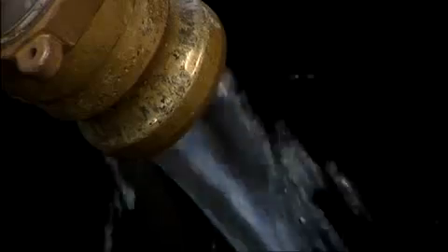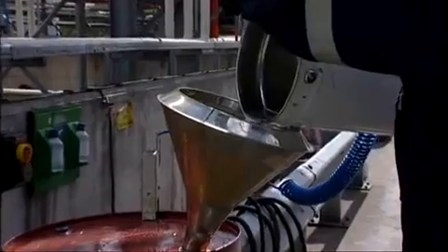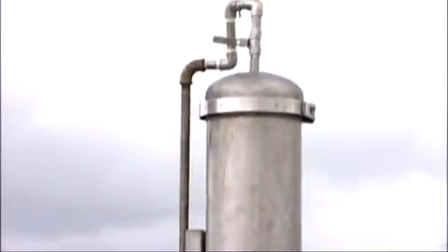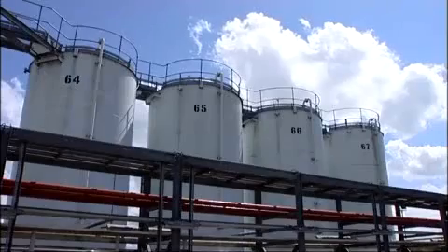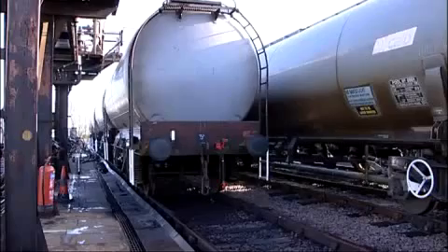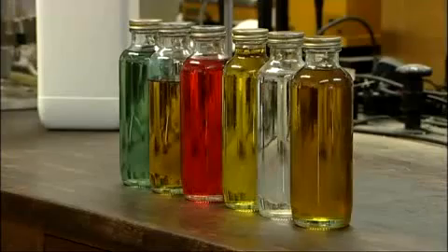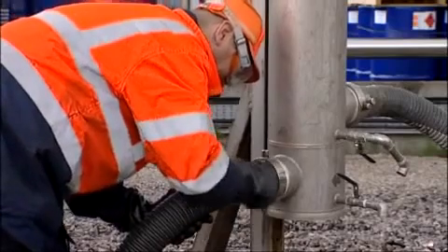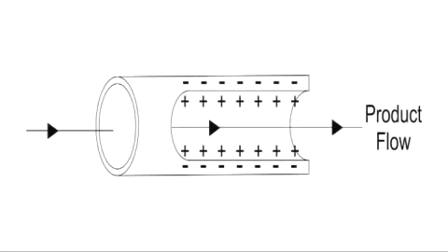Static electricity charge can be generated in solvents by liquid movement such as flow, mixing, pouring, pumping, filtering or agitation operations, where the movement separates electrical charges which may accumulate in the liquid and the containment system, such as pipes, tanks, drums, road tankers, rail cars and ships. If either of the materials is a good insulator, or the plant is isolated from earth, electrostatic charge will accumulate. A good example is liquid flowing through a pipe.